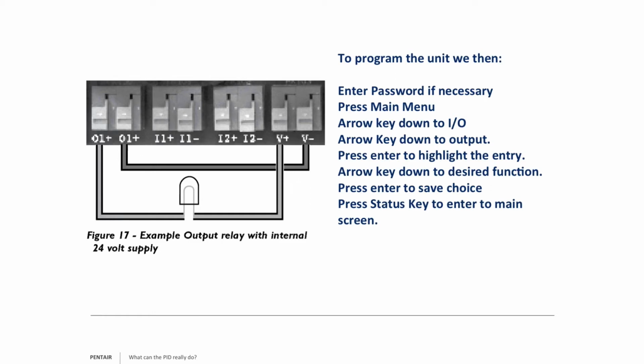It's important to remember also that you can use the onboard voltage to do so, but it's only 20 milliamps. So I typically tell customers, though you can do it, most outputs are going to be 115 or 230 volt, but it's a non-inductive load. Do not try to start a motor with this. You can trigger voltage to go down to a pump relay and start a pump that way, but the inrush current will damage our relay.